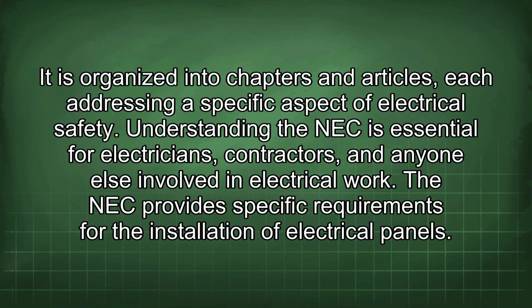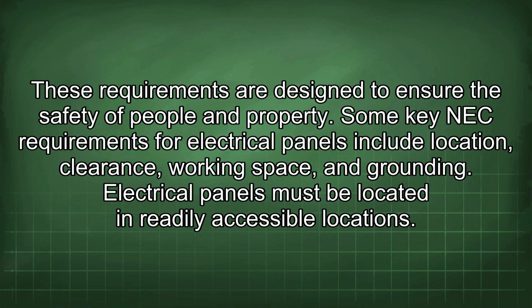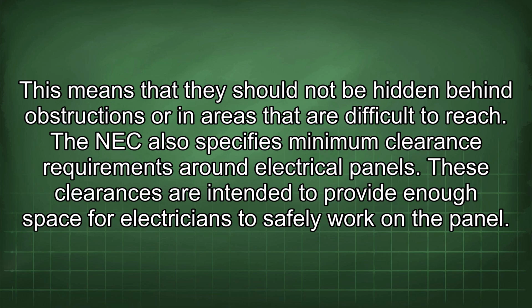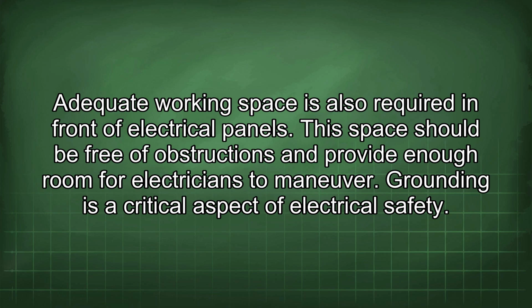The NEC provides specific requirements for the installation of electrical panels. These requirements are designed to ensure the safety of people and property. Some key NEC requirements for electrical panels include location, clearance, working space, and grounding. Electrical panels must be located in readily accessible locations. This means that they should not be hidden behind obstructions or in areas that are difficult to reach. The NEC also specifies minimum clearance requirements around electrical panels. These clearances are intended to provide enough space for electricians to safely work on the panel. Adequate working space is also required in front of electrical panels. This space should be free of obstructions and provide enough room for electricians to maneuver.